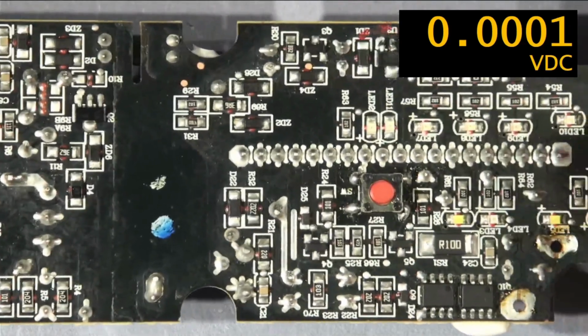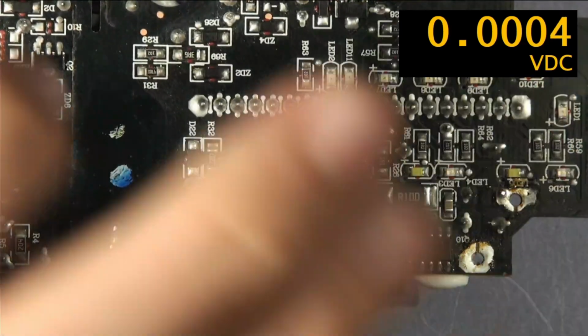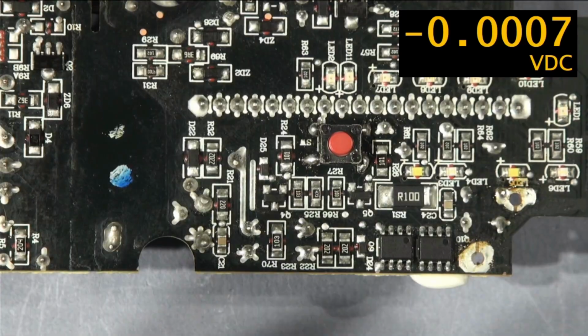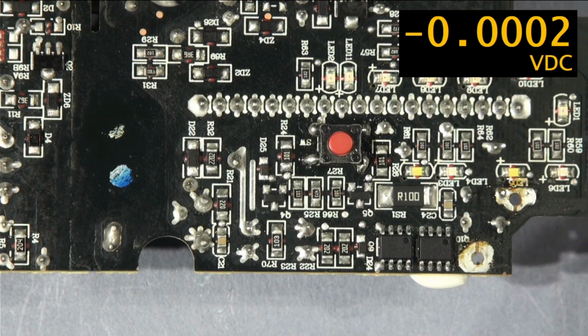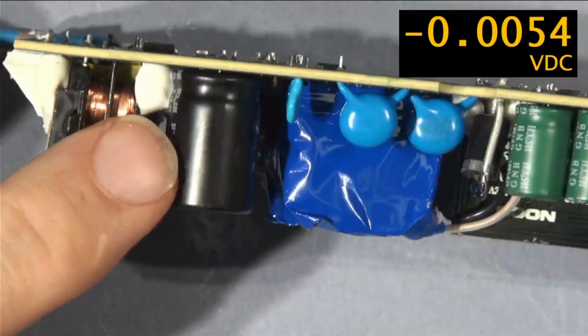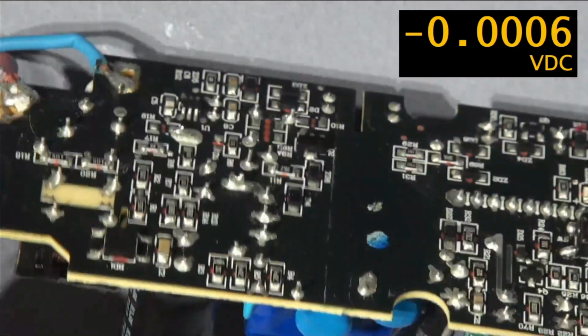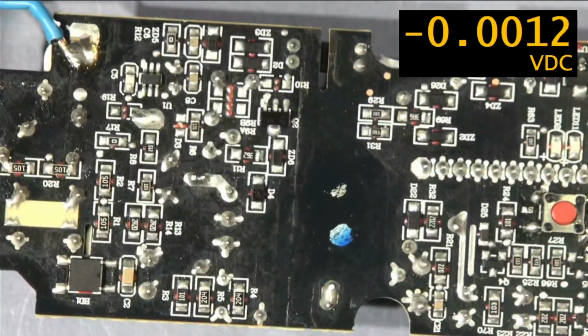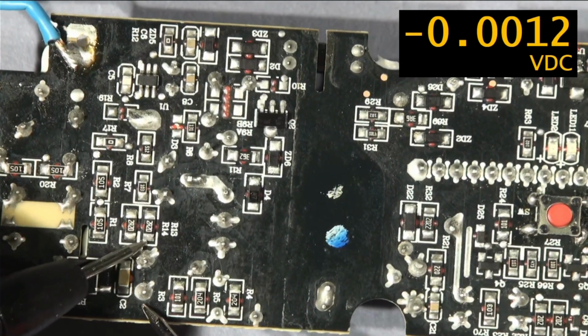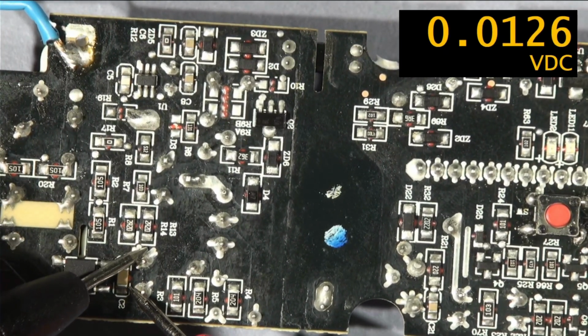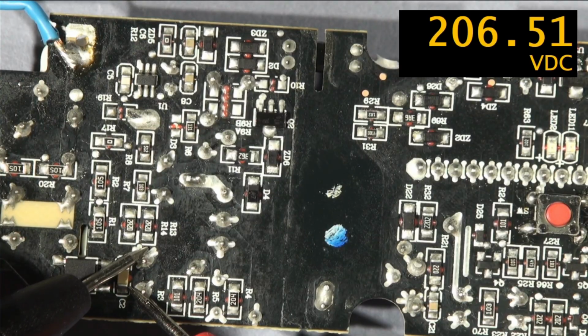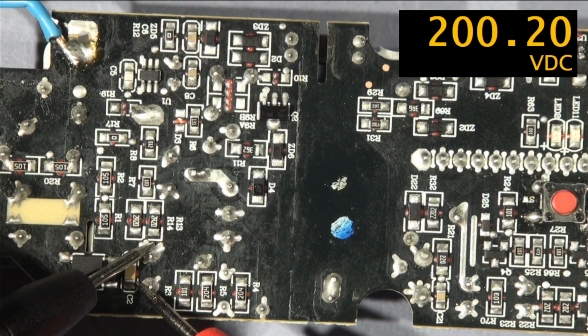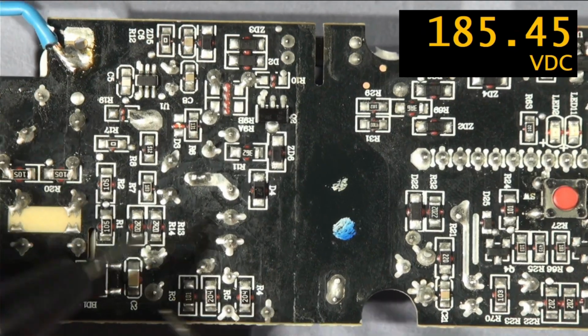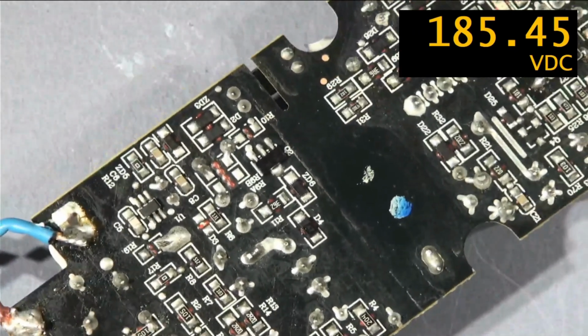So what I'm going to do is turn the power off. You need to leave it for a few minutes for any dangerous voltages on this capacitor to dissipate. I don't know what's on there at the moment - let's check it to see what it's reading now. Yeah, we've got 206 volts on there at the moment, which you don't really want down your shirt, so I'm just going to short that out.